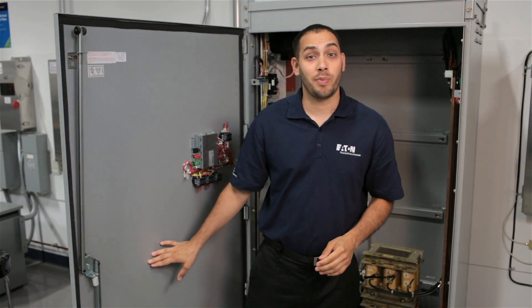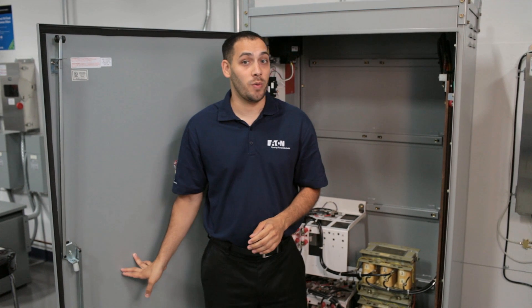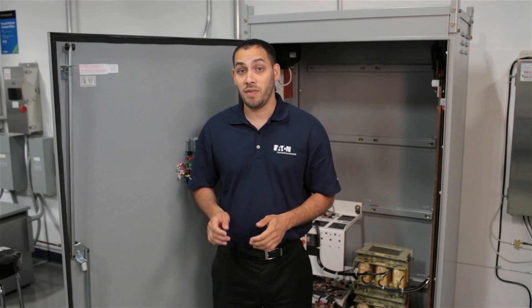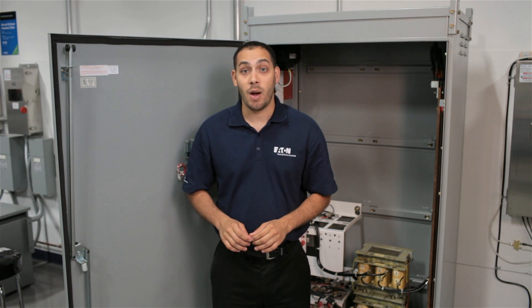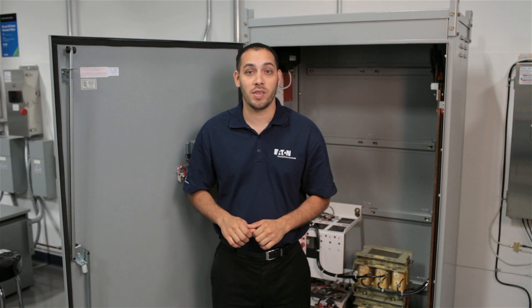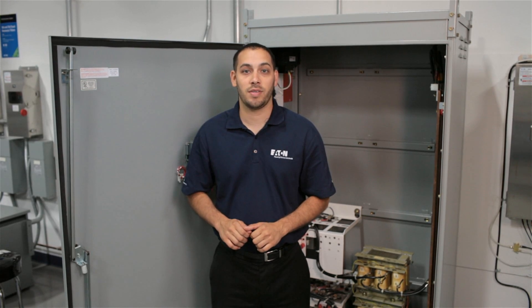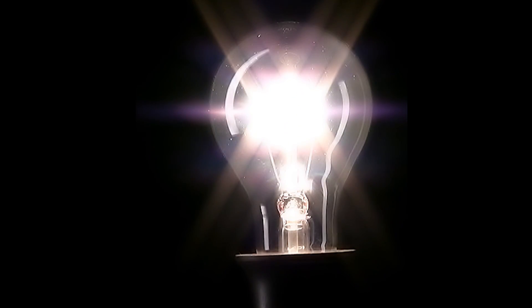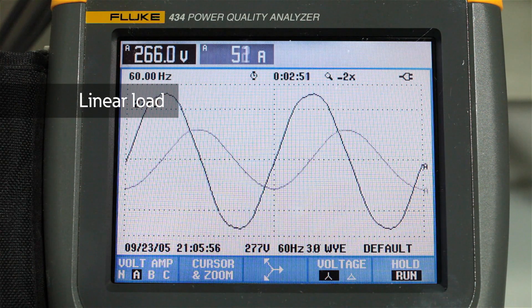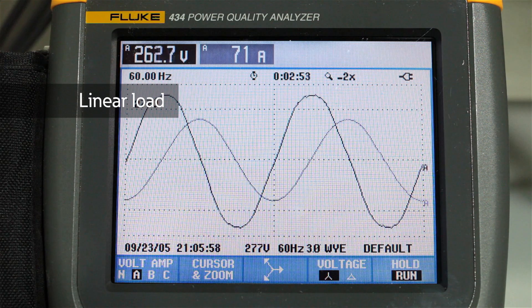Harmonics are defined as the presence of distortion in the voltage and current waveforms. Every system is capable of receiving and creating some harmonic distortion. However, today we see the presence of harmonic problems as a more common occurrence due to the significant use of electronic loads. Traditional loads like a light bulb or standard driven motor do not create harmonics. We call these loads linear because the current they draw looks similar to the voltage.